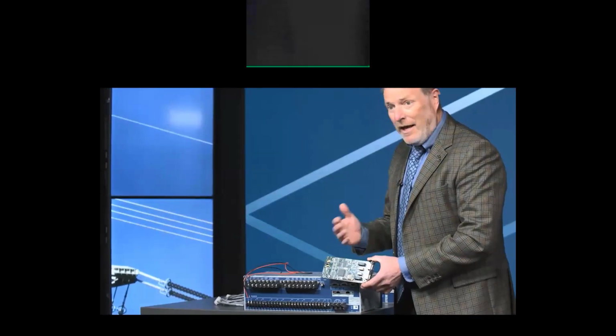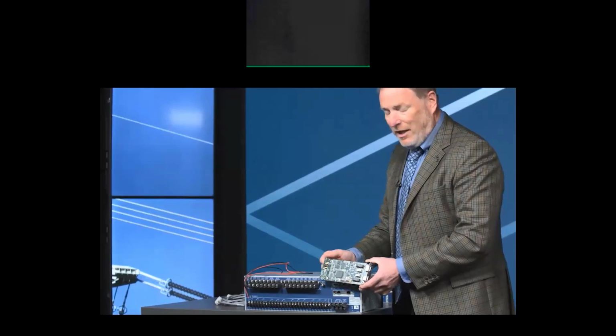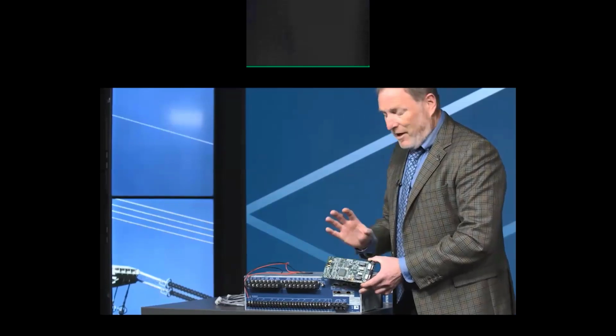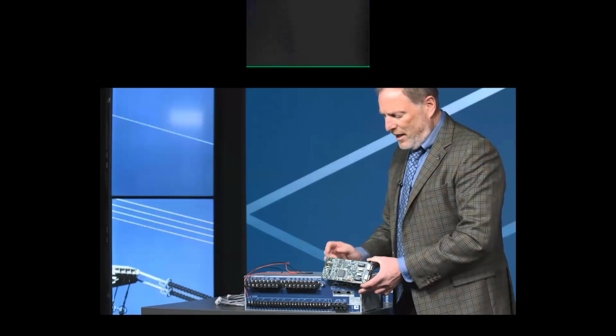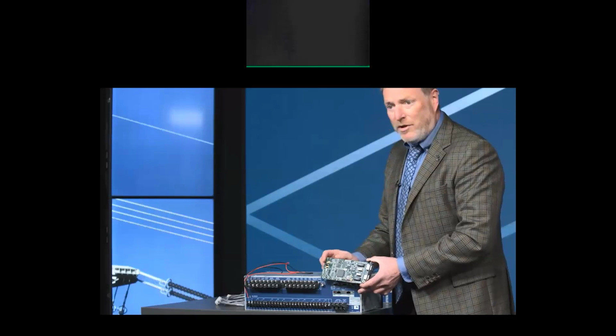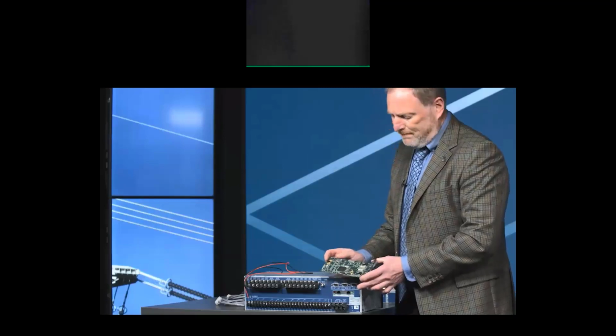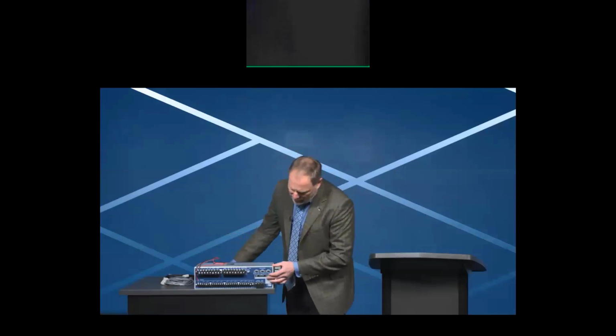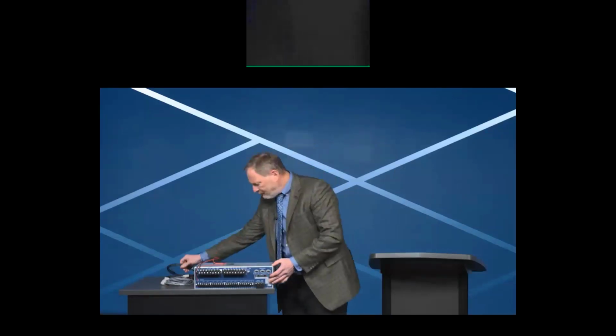And of course, all the competition and the other devices since then have all the Ethernet enabled by default, which is a real challenge for control systems because we have to hunt down and find all those communications and open Ethernet ports and disable them in the substation.